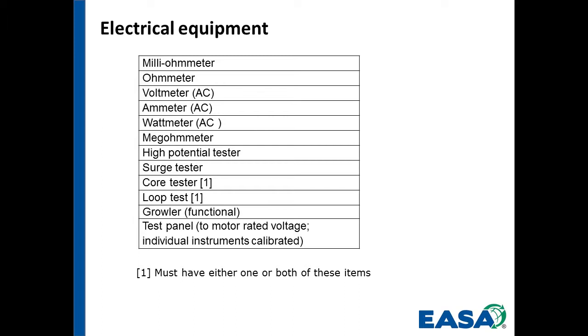A wattmeter, depending on what you're doing, might be built into a core loss tester as a machine, or if you're doing a loop test, you'd need a separate wattmeter. If you're doing space heater testing that's required in the program, to check the space heaters, you can check voltage and current, or you could check wattage. So if you're checking your space heaters with voltage and current, and you have a wattmeter built into your core loss tester, then that covers your wattmeter needs, and you may not need a separate wattmeter then.